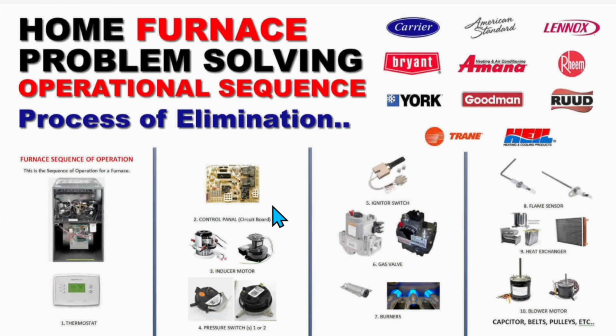Okay, let's do a process of elimination using our operational sequence knowledge. Number 1, we have a call for heat. If nothing happens here, you can pop this off and jump it right here. And if it works, you know it's the thermostat. You can also jump it right here on the control panel. You can also order a similar one so you don't have to mess with the wires. Pop it on. If it works, then you know it's the thermostat, it's the control panel.